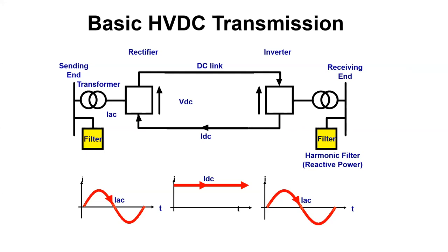Similarly, there is a filter shown. It also has a technical reason. In case of LCC, it limits the transfer of harmonics generated by the converter into the AC grid, as well as providing reactive power support to compensate the reactive power absorbed by the converter. Whereas in case of VSC, most of the time this is not even required. Like I mentioned at the start of the presentation, I'm not going to go into technical design details today. I got this picture just to give you an overview of some of the HVDC equipment.